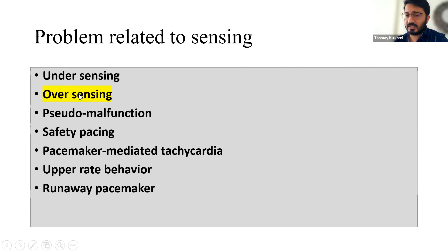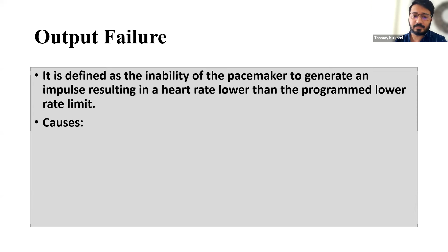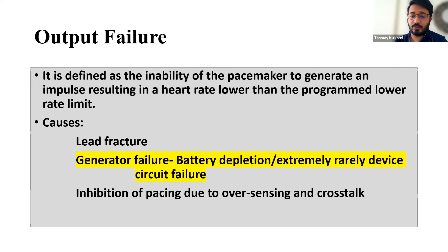Output failure is defined as the inability of the pacemaker to generate an impulse, resulting in a heart rate which is lower than the programmed lower rate limit. Causes are lead fracture, generator failure, which might be due to battery depletion, or extremely rarely device circuit failure, which was the working diagnosis for this case. Inhibition of pacing due to oversensing and crosstalk is also one of the causes of output failure.